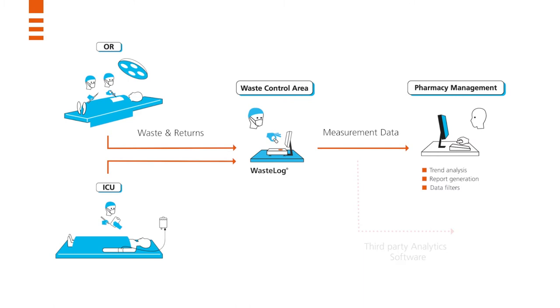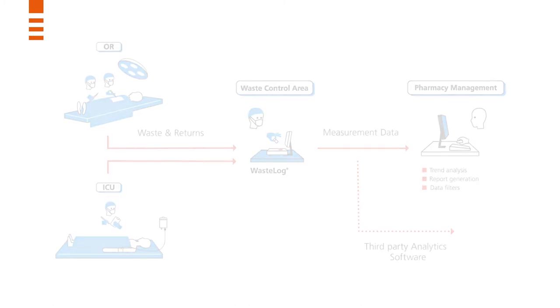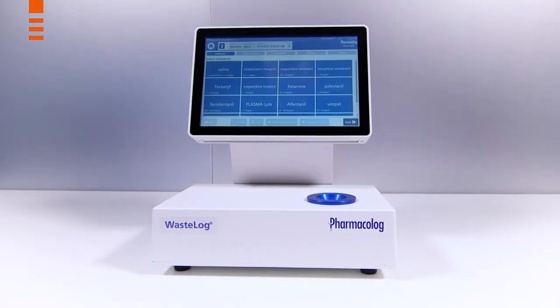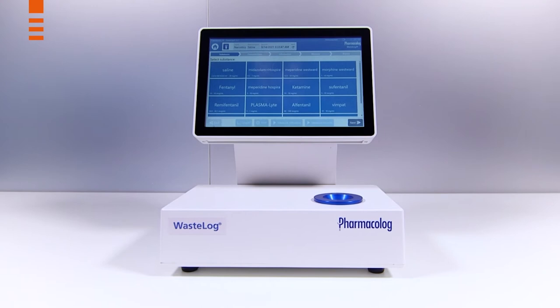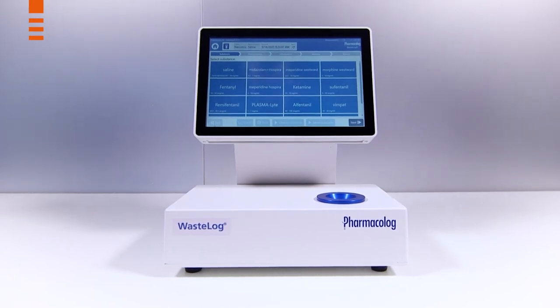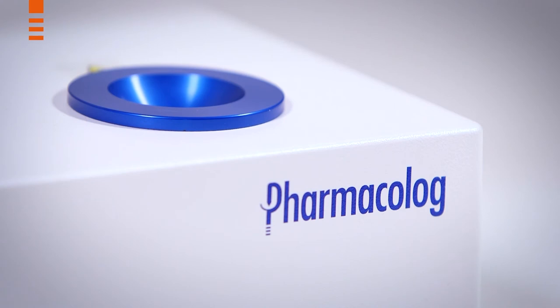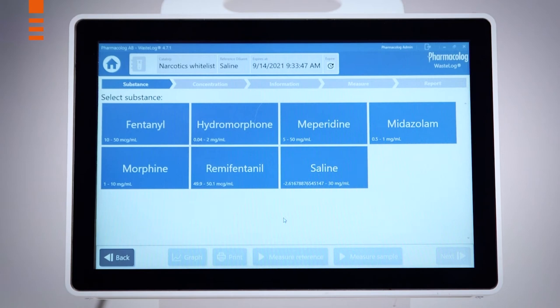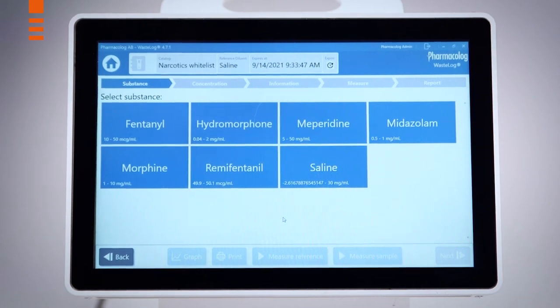WasteLog also integrates with any existing third-party data analytics software. Providing verification within seconds, WasteLog can easily fit into your current workflow. The technology is based on light absorption spectroscopy combined with unique software and pre-installed calibration libraries of your facility's most used substances.